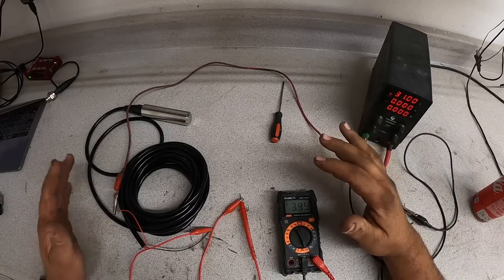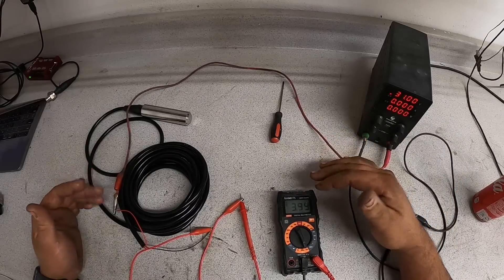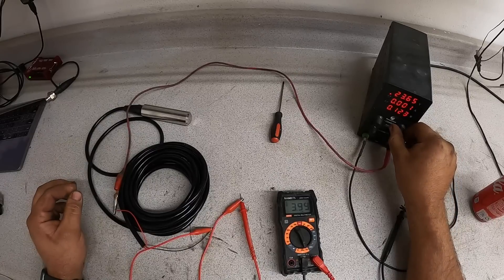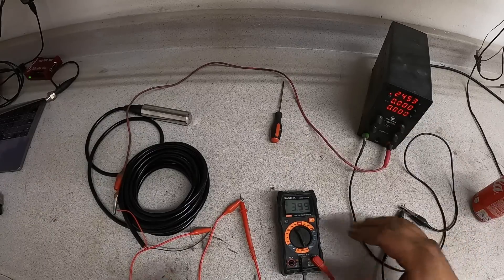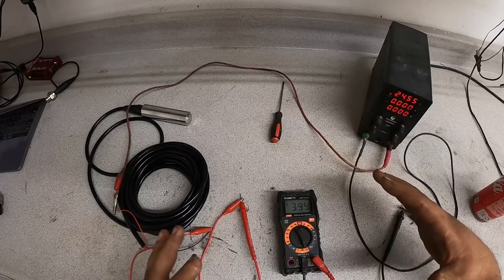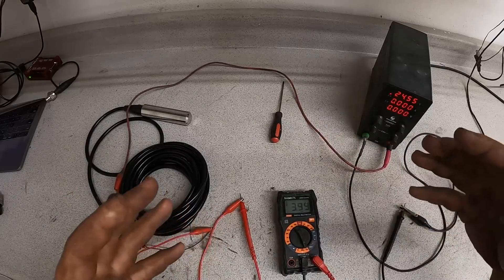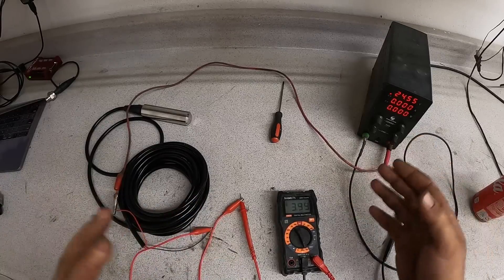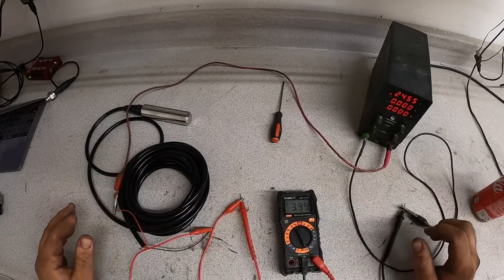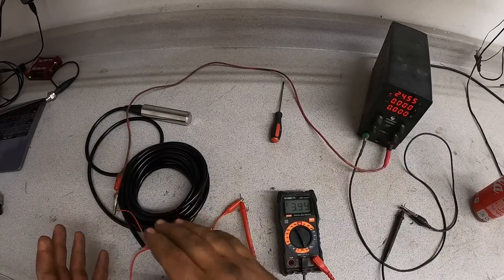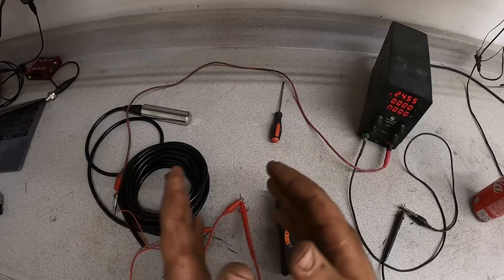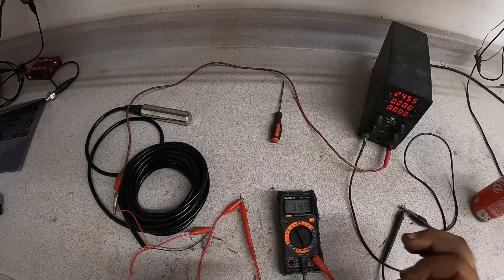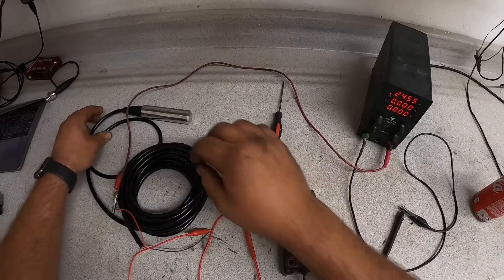That's one of the really good things about the 4 to 20 milliamp sensors is that the input voltage is not important. These are nominally 24 volts. But you can simply have a 24 volt battery, whether it be a stack of AA batteries or however. And if the batteries are kind of overcharged or get way undercharged, the sensors still read very correctly.